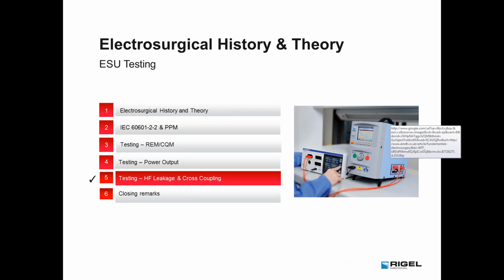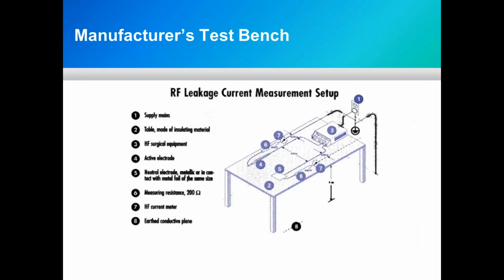So we've done REM, we've done power output testing on 4 different energy ports: Monopolar 1, Monopolar 2, Bipolar, and LigaSure. LigaSure, of course, is bipolar in nature. Now we're going to jump into high frequency leakage and cross coupling testing. So if you ever have the opportunity to visit one of the generator manufacturers, they all have this infamous wooden table with their generator and all the leads very well defined as to the layout of where they need to be.